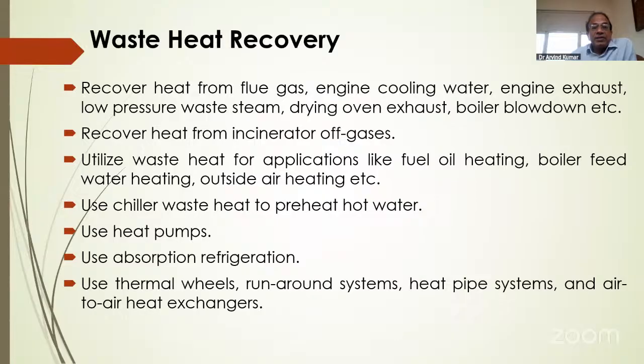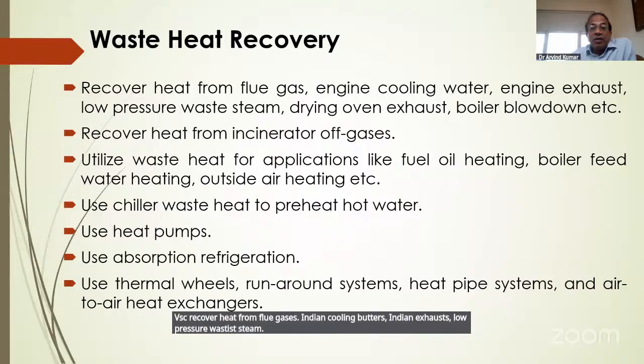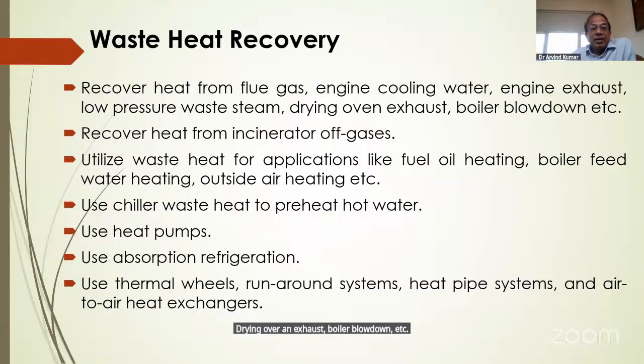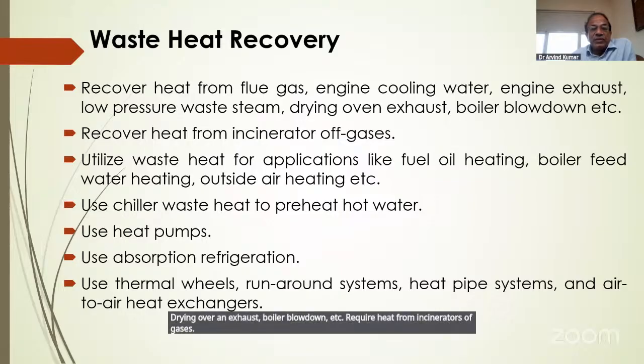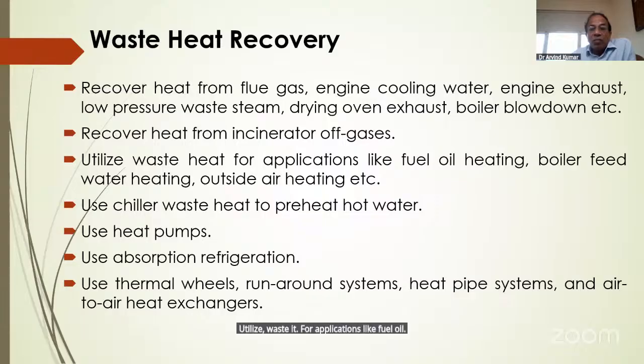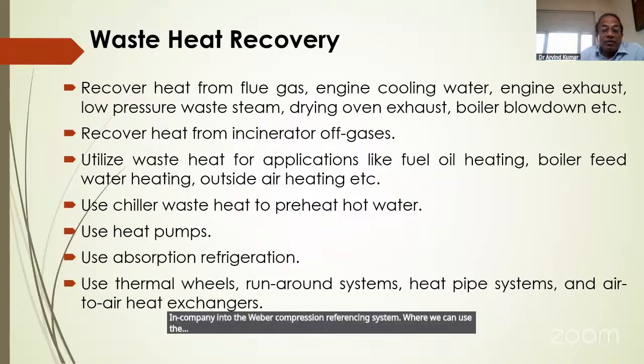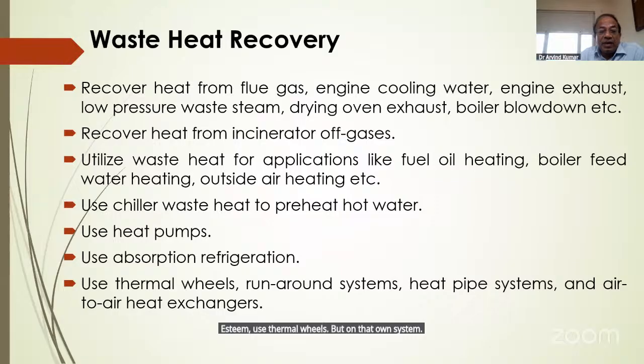Waste heat recovery: recover heat from flue gases, engine cooling waters, engine exhaust, low pressure waste steam, drying oven exhaust, boiler blowdown, etc. Recover heat from incinerator gases, and utilize waste heat for applications like fuel oil heating, boiler feed water heating, and outside air heating. Use chiller waste heat to preheat boiler water. Use heat pumps rather than directly using electric energy for heating. Use absorption refrigeration in comparison to the vapor compression refrigeration system, where we can use the waste heat of steam. Use thermal wheels, run-around systems, heat pipe systems, and air-to-air heat exchangers.